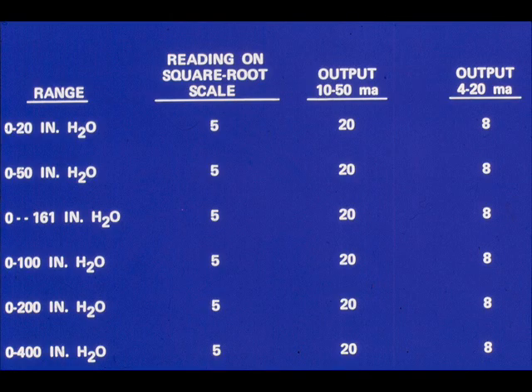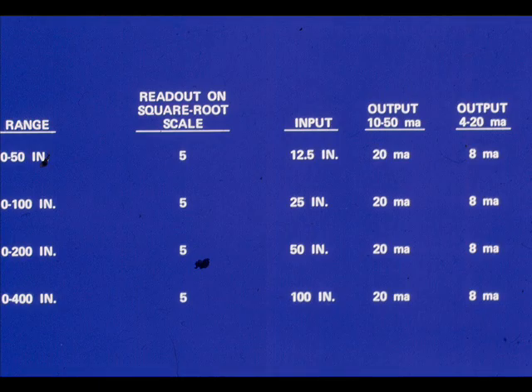Note that for a given reading on a square root scale, the output is the same regardless of the range. To give a reading of 5 on the square root scale, the input to each transmitter is different. However, in each case, the reading of 5 represents 25% of the input span. This has been a brief review of flow scales studied in other modules.